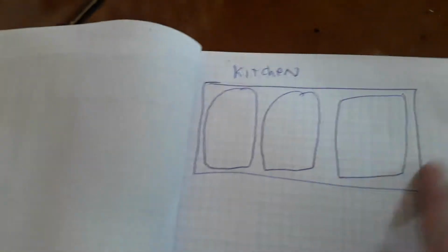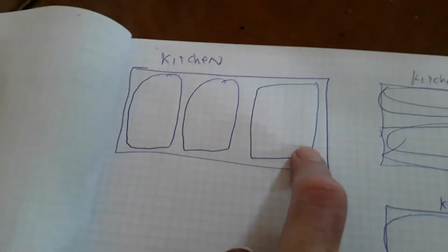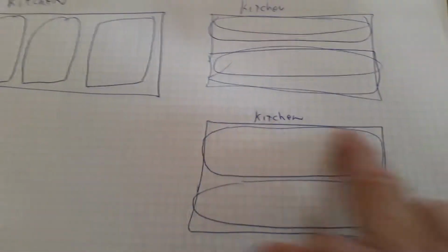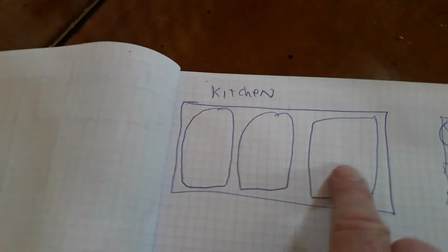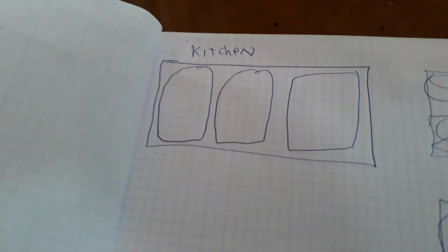And we want to end up with a map, something like this, where we take the kitchen. If we have a plan of the house, it's ideal, but if we have the kitchen, then we'll know whether there are 2 loops in it, like in this shape, maybe 1 here and 1 here, or 3 as in this instance, in here, here and here. So we'll know eventually by measuring. Once we see the floor temperatures rising at the particular spots, then we can go around in a more general area to draw where's hot and where's cooler, to give us this map of what we're going to end up with.